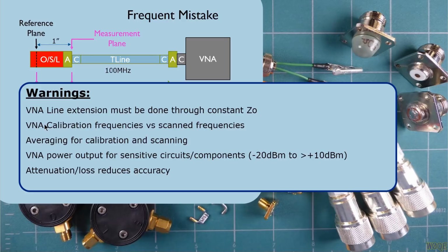And the only thing you can do, when you get something you think might be a little bit incorrect, is to increase the number of calibration frequencies. It takes longer to calibrate. It generally doesn't hurt you to have more calibration frequencies because it's just in software.